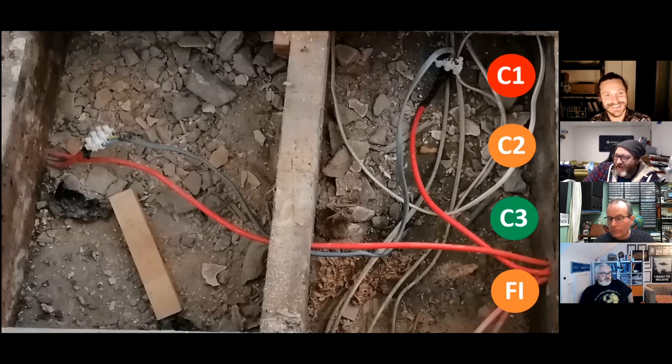So what you're saying is that if this was an enclosed floor, essentially you've got some form of fire barrier. It depends on obviously the barriers. But obviously if this is under the floor, then it depends on the fire risk as to where it goes. I mean, obviously fire propagates on the ground as well. And we don't know if there's any downlights that could cause fire within the void itself, or any other risks in the void and things like that. I'm not a big fan of seeing, and again, it's my OCD, but I don't like seeing rubble and dirt and dust and wood shavings and stuff left under floors.